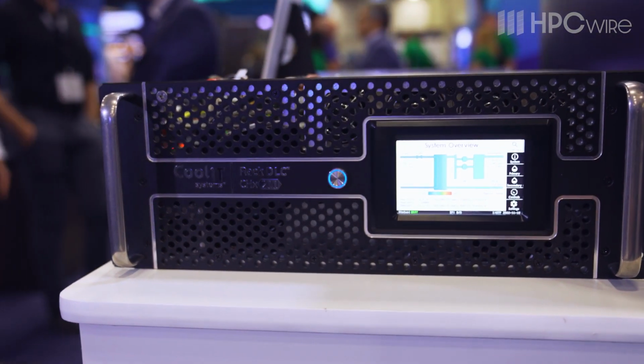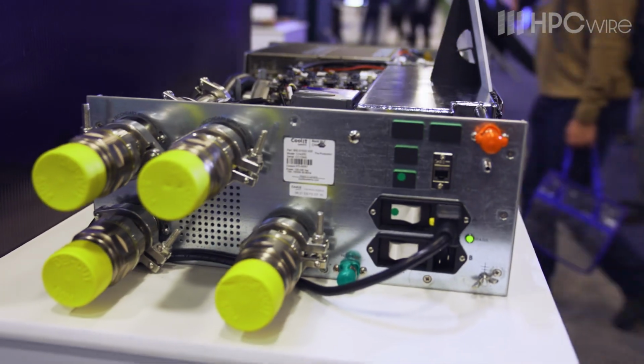CoolIT is also showing our updated CHX200. What we've done in this unit is put a 2-way valve into the system instead of a 3-way valve. The implication of this is that it's optimized for heat recovery applications. We had a lot of customers in Europe looking to reuse the heat from data centers, and by putting that 2-way valve in there, we're able to raise the return water temperature back up so they can use that water for something useful, like heating buildings.